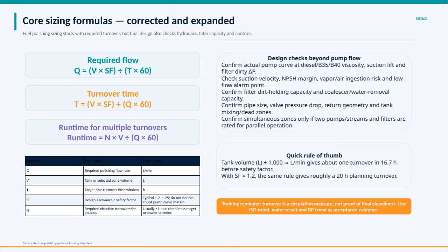When planning for multiple turnovers, for thorough cleanup, runtime is calculated by multiplying the number of turnovers by the volume, then dividing by flow rate and converting to hours. It's important to pay attention to the design allowance or safety factor, typically between 1.2 and 1.25, to ensure a margin of safety without overestimating pump capability. The number of turnovers, represented by N, usually exceeds 1 and depends on cleanliness targets.